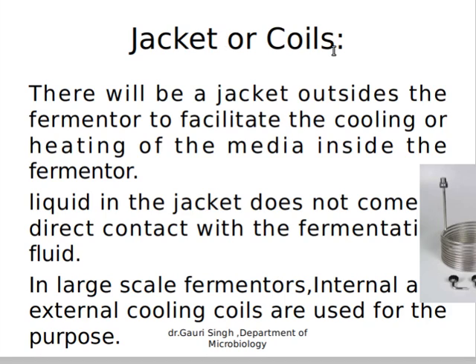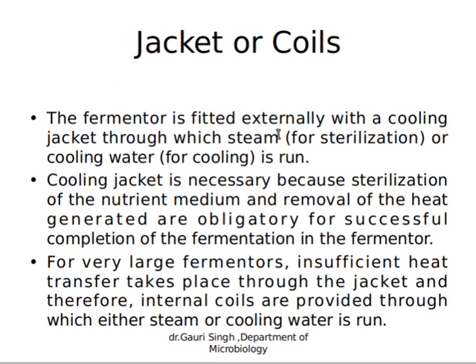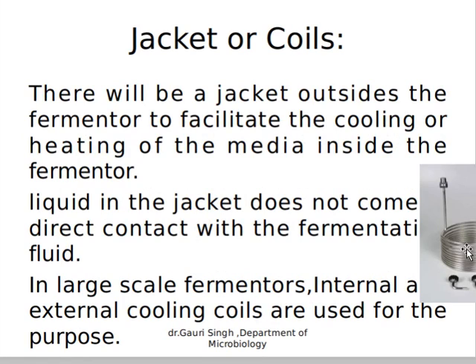Now, jacket or coils. The fermenter is fitted externally with a cooling jacket through which steam for sterilization purposes or cooling water for cooling purposes runs. The cooling jacket is necessary because sterilization of the nutrient medium and removal of the heat generated are obligatory for successful completion of the fermentation in the fermenter. It means to control the temperature inside the fermenter, there is a jacket or coils. Generally, jackets are present in small scale fermenters and coils are present in large scale fermenters. This is the coil. Liquid in the jacket does not come in direct contact with the fermentation fluid.